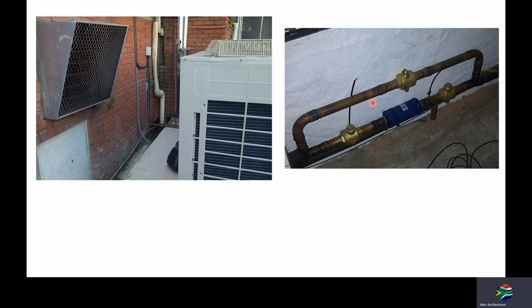The problem with this is oil return. So ultimately you would want the pipe to run on the bottom with the valve, so gravity can support the oil and help you get your oil back to the compressor.